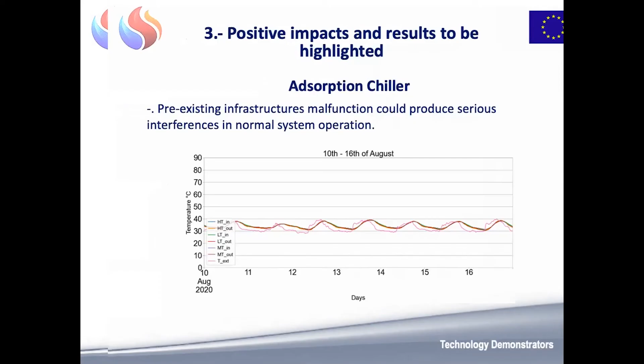As I said, this project is not yet finished, but I will try to get some conclusions from the operation of the system during the last year. The first and probably most important one is that the adsorption chiller is able, under proper conditions, to operate providing very good COP values. Efficiency is quite close to the technically estimated one by the manufacturer, who is Fahrenheit. It is close to 0.5. Here we can see some figures with different recooling temperatures, but they tend to converge on that value.